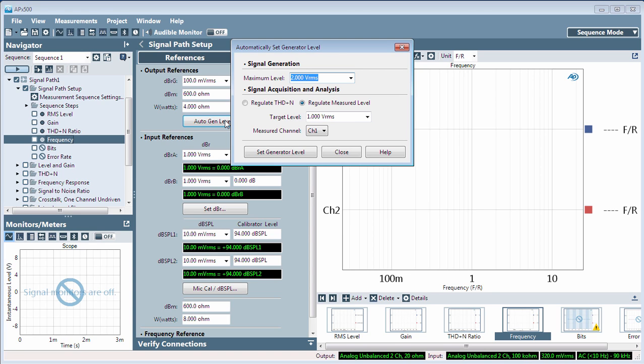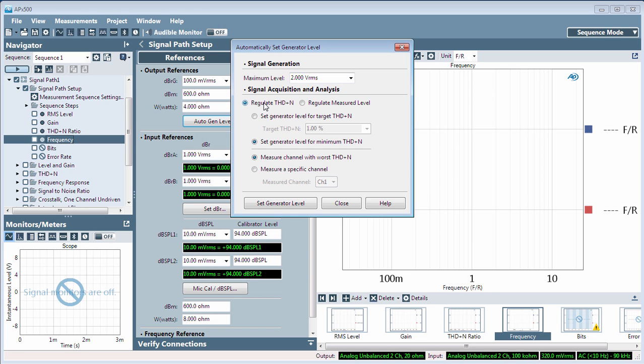The dialog provides an interactive, regulated measurement to identify a generator level reference that corresponds to a targeted signal level or amount of distortion in the output of your device under test.